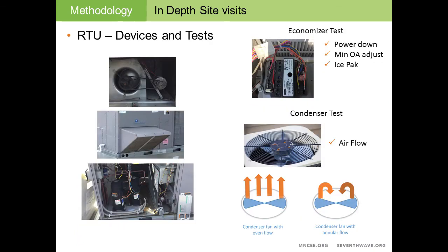For the RTU devices themselves, we were looking at the components of the systems. So we were looking at the condition of the fans, whether they were direct drive or, in the case of the upper picture here, belt drive. We also looked at the economizer, and we looked at the general condition of the compressor and heating section, again on that left side. To give you a little taste of some of the tests we were doing on the rooftop units, we had an economizer test that teased out the information of whether the economizers were working.